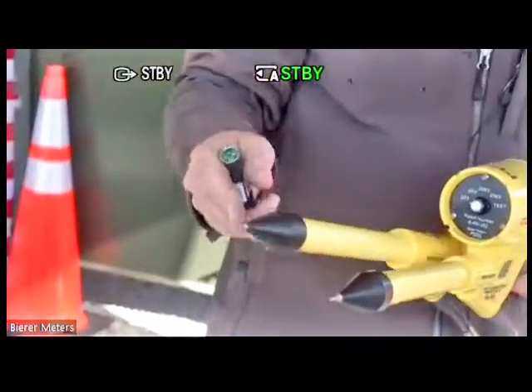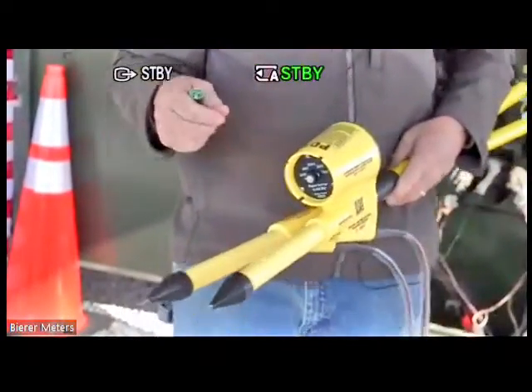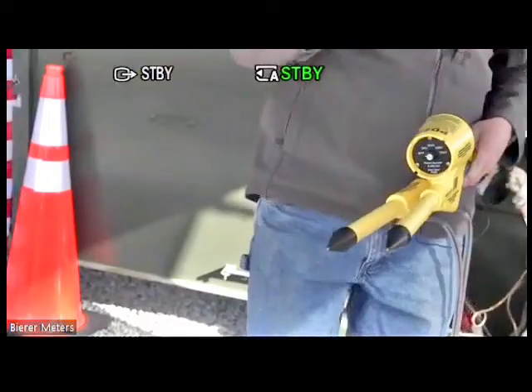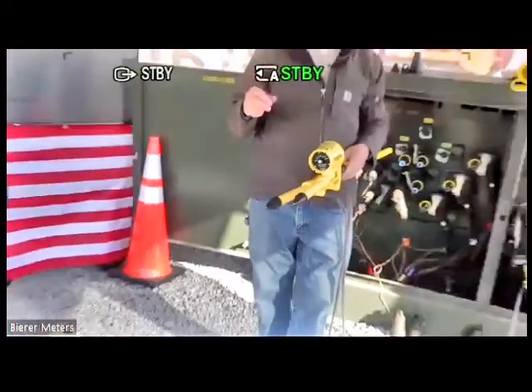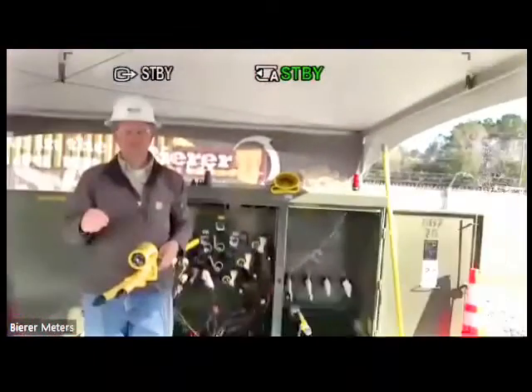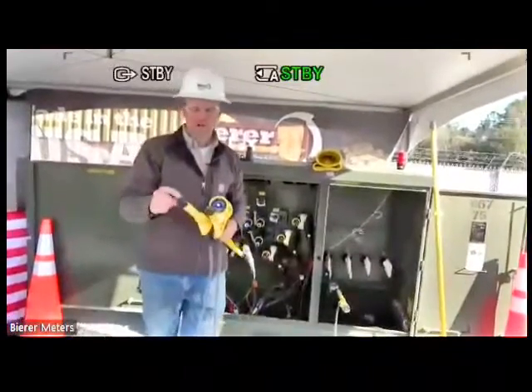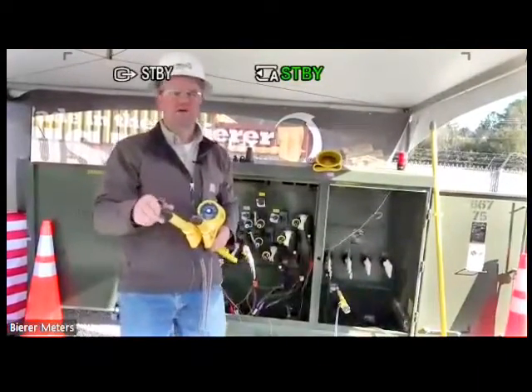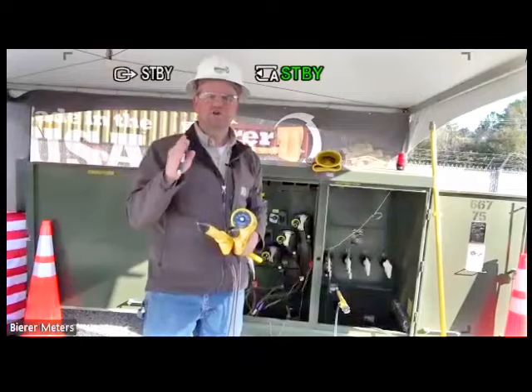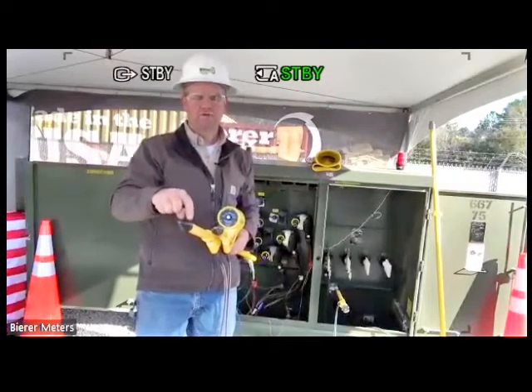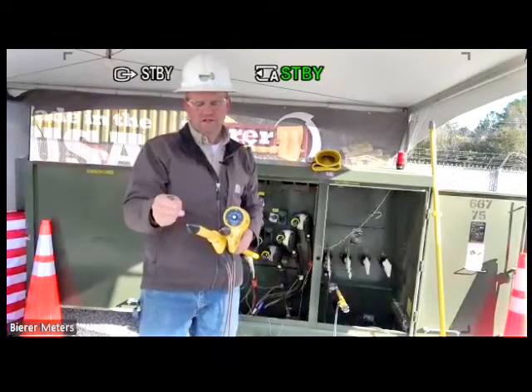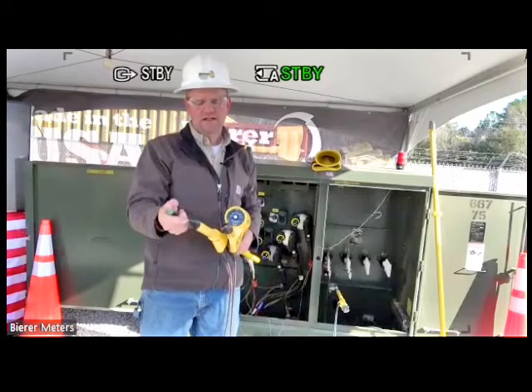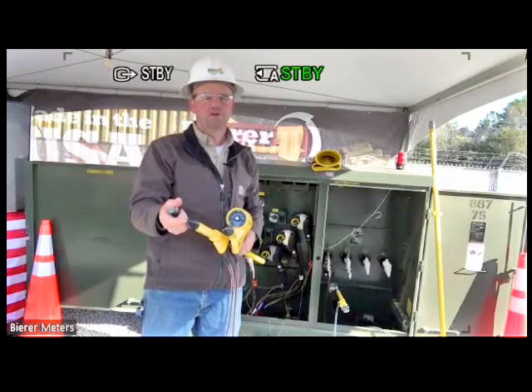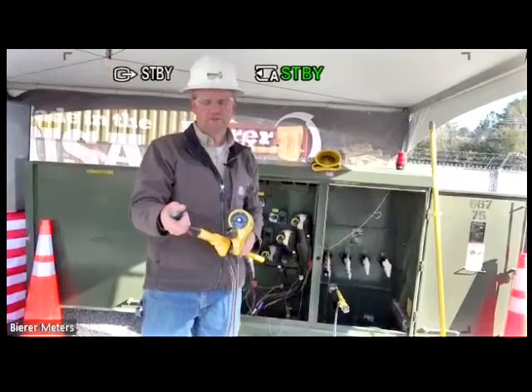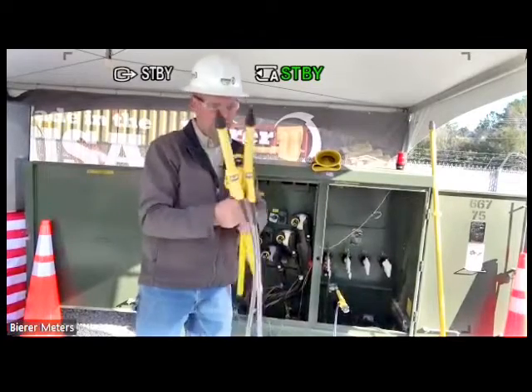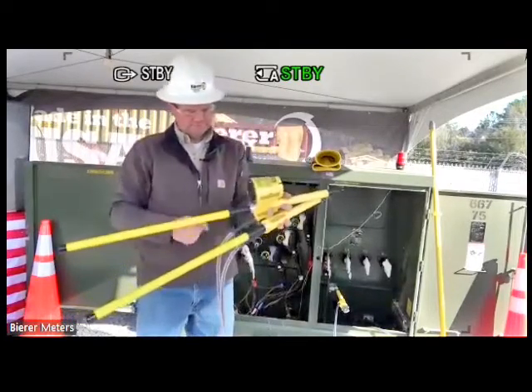It insulates that. So if you're utilizing this tool in a secondary disconnect, you don't want that large surface area to maybe cross connect, because those little fuse holders, whatever it may be in there, are in pretty close proximity. So we do have this adapter, it covers that. You have a much smaller surface area to work with here, so less likely to cross connect with anything.